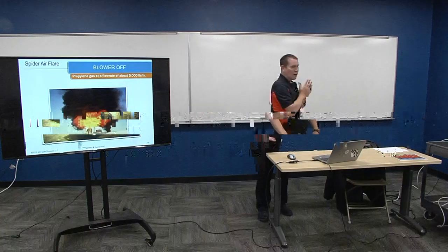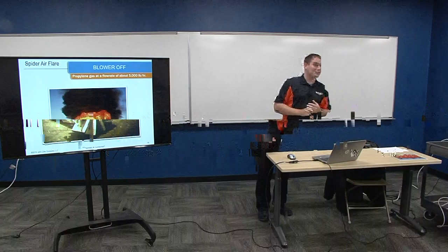So this is an air flare, again, back at our Peoria site. We've got 5,000 pounds an hour of propylene, pretty smoky stuff. And that's what most people used to do. They used to just flare it, and it would smoke, and it would be really ugly, right? Well, again, I said air flares are a good option. They're just not as good as steam.